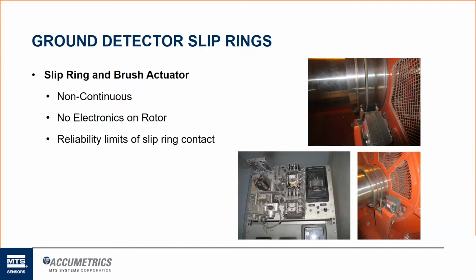So there's no electronics out on the rotor. It's non-continuous. You obviously have the reliability limits of a mechanical connection of those brushes touching on that slip ring. They need to be replaced at least once a year, a couple times a year. We run into a lot of customers where that solenoid doesn't work anymore. It's not making a good connection, and there's no feedback to tell them whether there is or isn't a connection. You can see the receiver part of the electronics is very old. This system was probably designed and developed in the 50s or 60s. So it goes back a very long time, and there's almost no serviceability of this. Customers can't find support for this product.